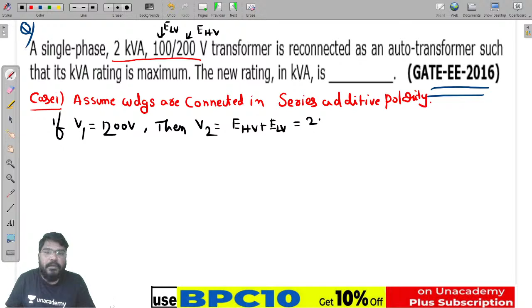K is equal to LV of auto transformer divided by HV of auto transformer. Let us calculate: K is equal to LV of auto transformer, which is 200 upon 300, that is 2 by 3. The value of 2 by 3 is 2 divided by 3, which is 0.66.